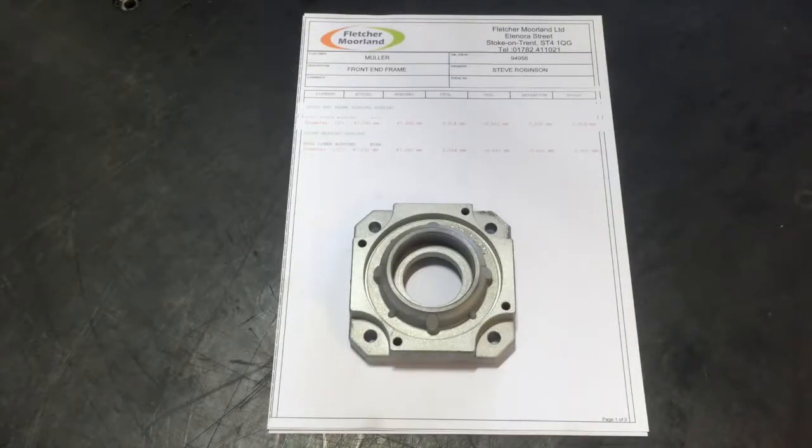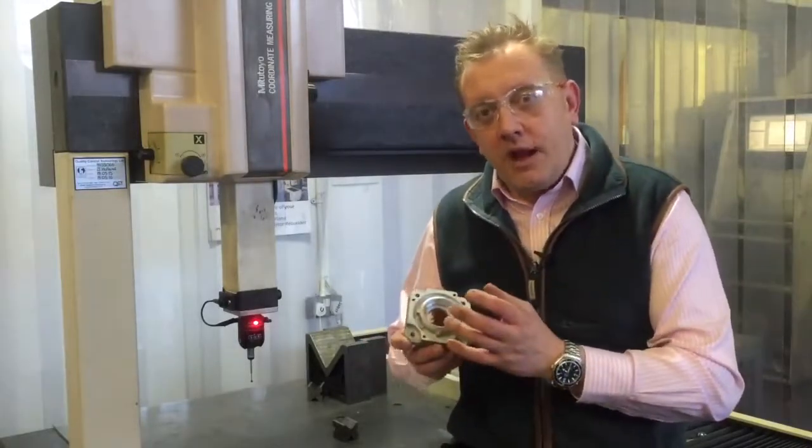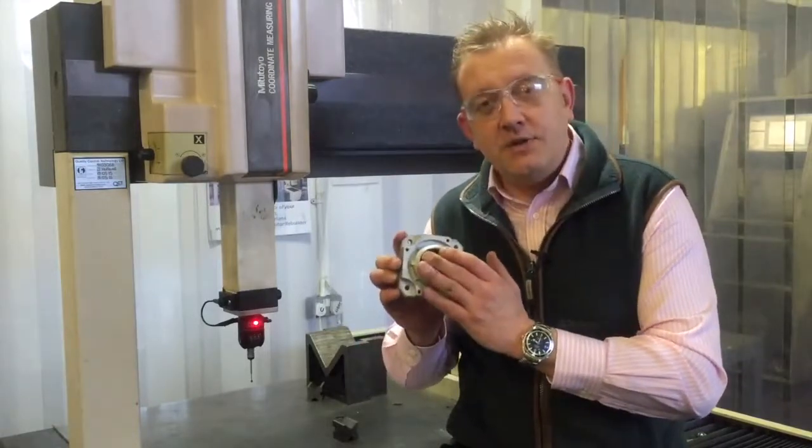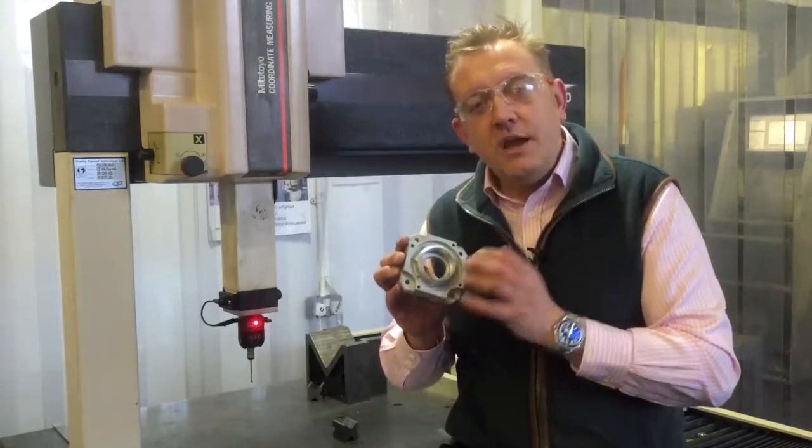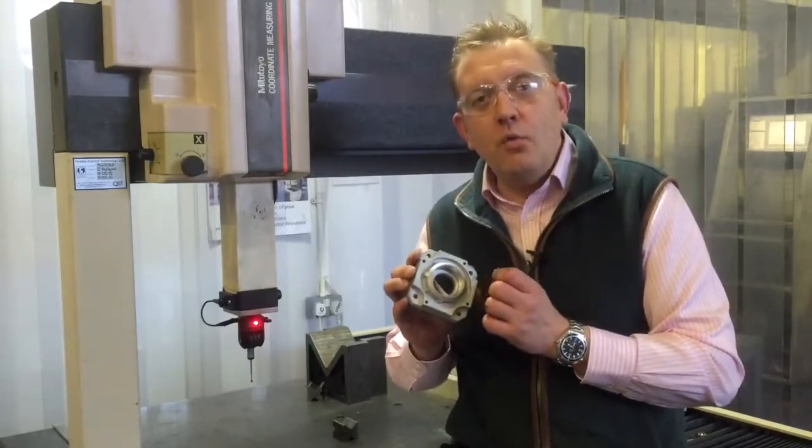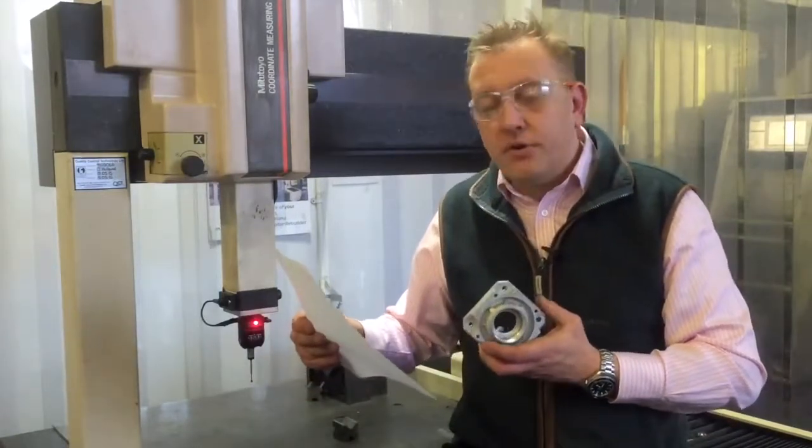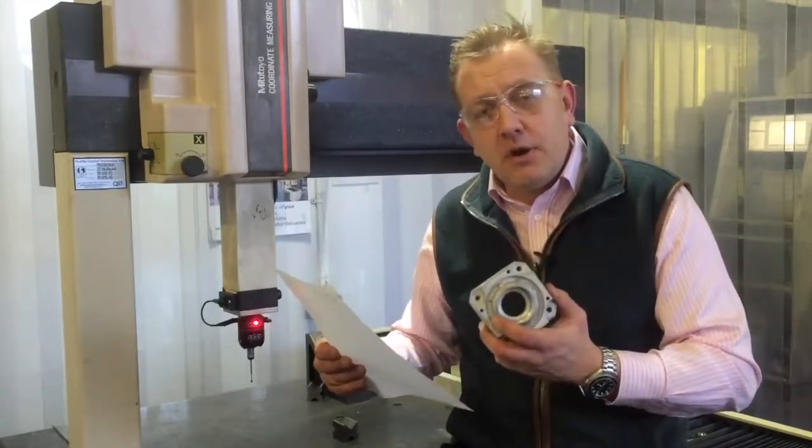All measurements have now been taken for this servomotor and what we have found is the drive end frame, the bearing housing there is oversized. I would just like to explain what it means when we say the bearing housing is oversized. It is where the bearing sits in this housing here. There is a tolerance and the upper tolerance for this bearing housing is 47.014mm. We have measured this and it is 47.030mm, which is 0.016mm, 16 microns.